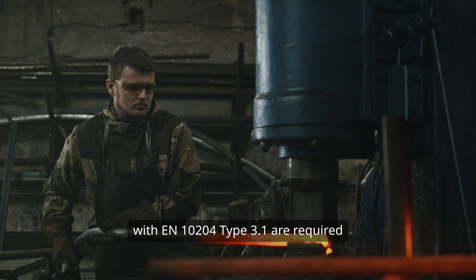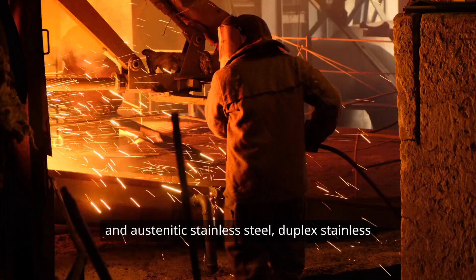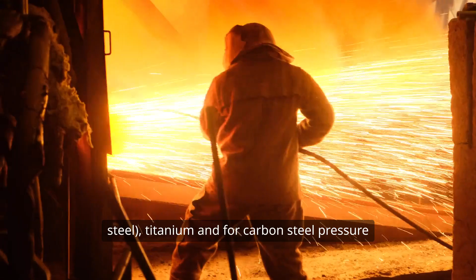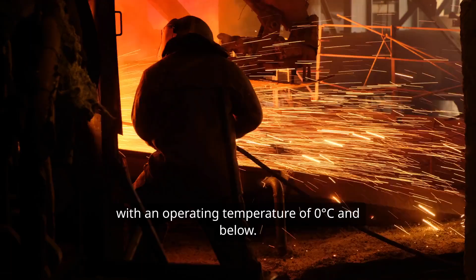2.8.6. Material certificates shall be in accordance with EN 10204 Type 3.1 are required for pressure-containing parts of low and high alloy steels, martensitic steels, ferritic and austenitic stainless steel, duplex stainless steel, titanium, and for carbon steel pressure-containing parts in hydrocarbon services with an operating temperature of 0 degrees Celsius and below.